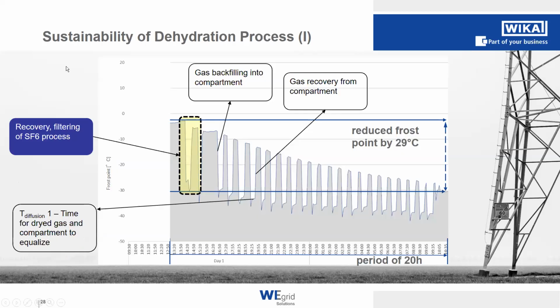When we now look at a chart of how this evolves over time, like you can see here over a period of 20 hours, this is our complete process of recovering the SF6 and then filtering and filling it back into the compartment. What happens is, when we fill the gas back into the compartment, our frost point, which is the dew point we talked about before, is getting higher. And when we backfill it and then recover a new portion of SF6, the dew point is rising again.